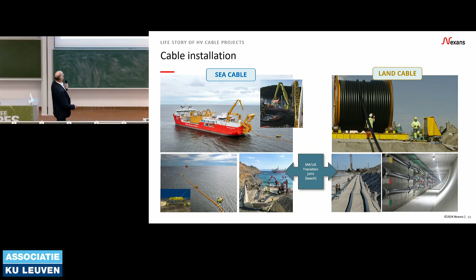Then you have to joint it. Once the cable is laid, you have to joint it, and this needs special techniques. To joint your cables, you need, for example, as you see here in the picture, a TIG/MIG system, because in this case we are using a copper enameled conductor. This is a conductor that gives you 15% more ampacity compared to copper at the same diameter or cross-section, which requires special welding techniques. Then there are the sealing ends as well. Sometimes the size is quite huge for people to manage. So we have to manage not only the electrical and mechanical parts of the installation, but also safety, because all these jointers have to work in a difficult environment, which can be extremely dangerous at times, especially when they work in substations where the connection bars are live.